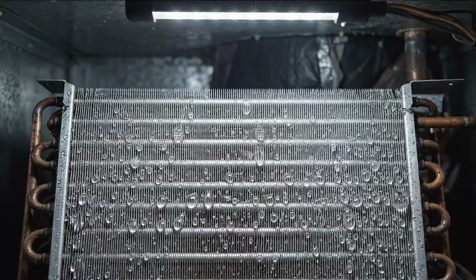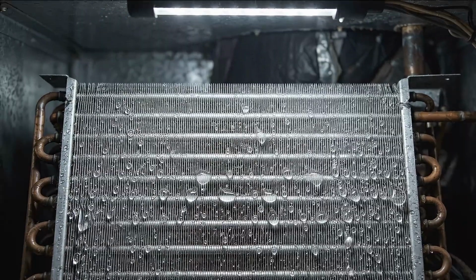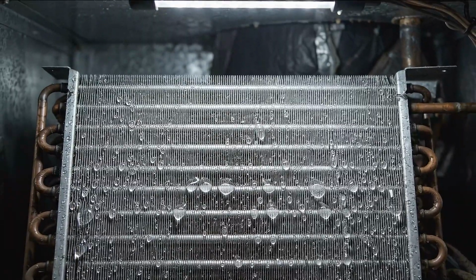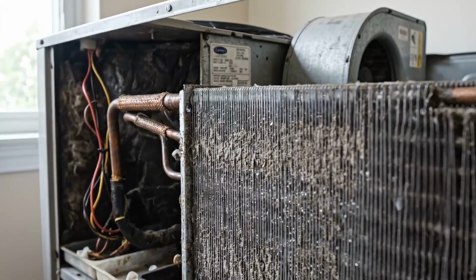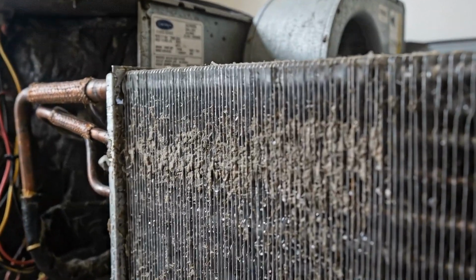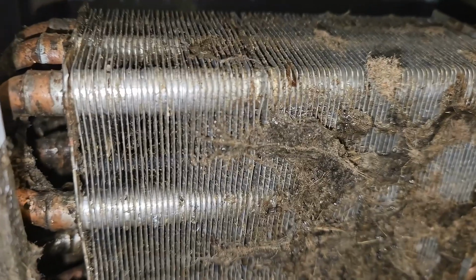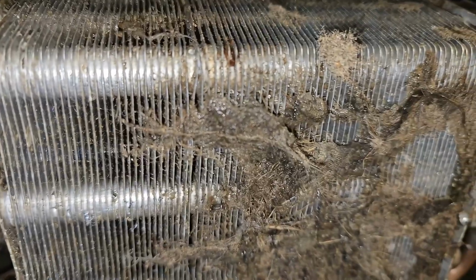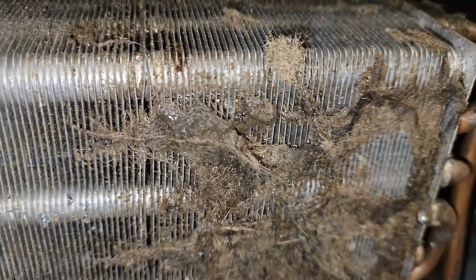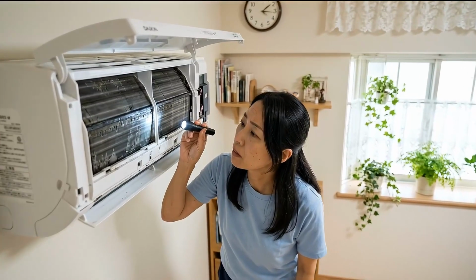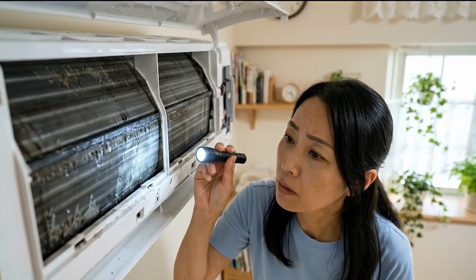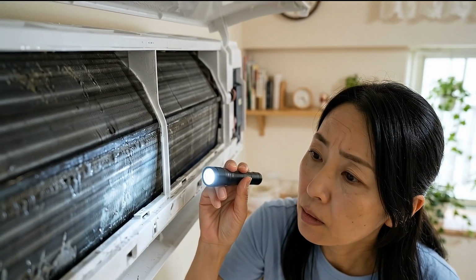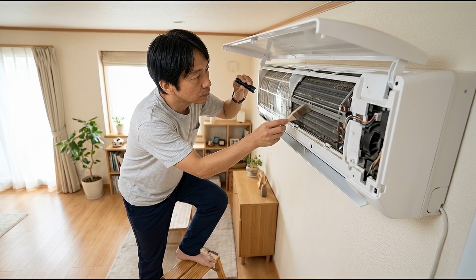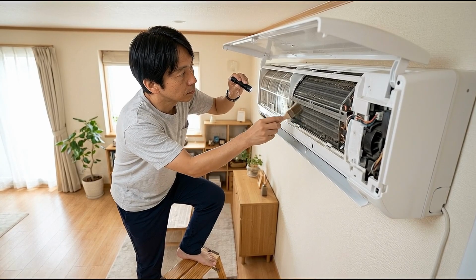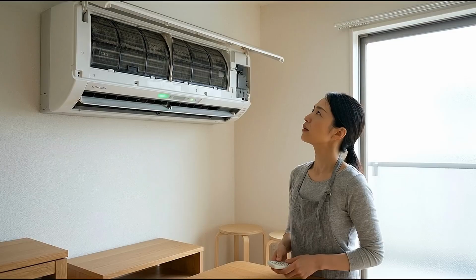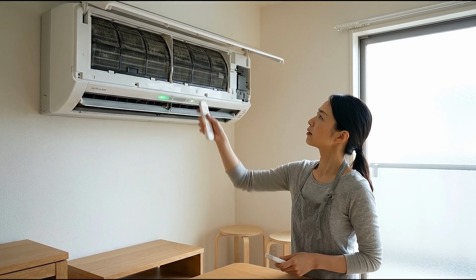And because the evaporator coil operates wet, condensation is always forming on its surface as it pulls moisture out of the air. That dust mixes with water and becomes a sticky layer that does not blow off the way dry dust sometimes does from the condenser. This is also where the mold problem starts, and this is exactly where the Japanese practice of naibu-kurin comes in. Naibu-kurin, written in Japanese as a compound of the words for internal and clean, is a function built into most Japanese air conditioners.